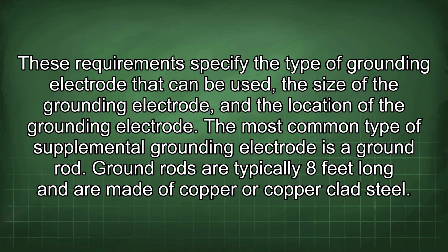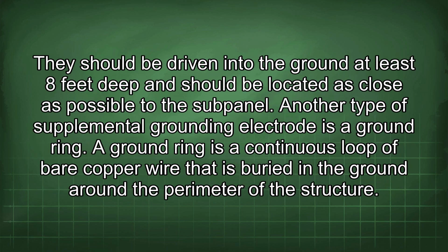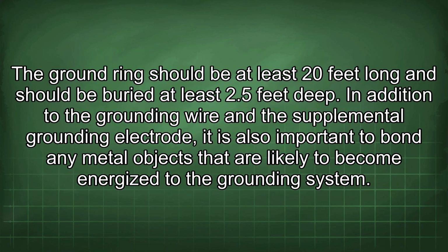The most common type of supplemental grounding electrode is a ground rod. Ground rods are typically 8 feet long and are made of copper or copper-clad steel. They should be driven into the ground at least 8 feet deep and should be located as close as possible to the subpanel. Another type of supplemental grounding electrode is a ground ring. A ground ring is a continuous loop of bare copper wire that is buried in the ground around the perimeter of the structure. The ground ring should be at least 20 feet long and should be buried at least 2.5 feet deep.